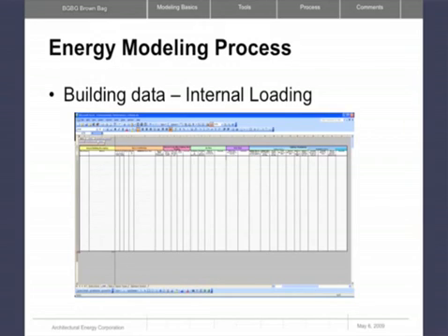And then what are the space conditions? Temperature set points, occupancy, how much lighting, internal equipment will I have, how many computers, that kind of thing. How much air do I need? What are the ventilation requirements that might be set out of Standard 62, for example, or whatever. For a lab building, how much exhaust air might I need, because this is a certain kind of really nasty stuff lab, and I have to have a lot of exhaust.